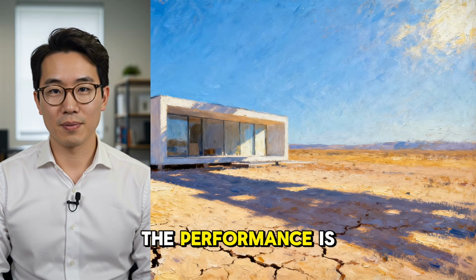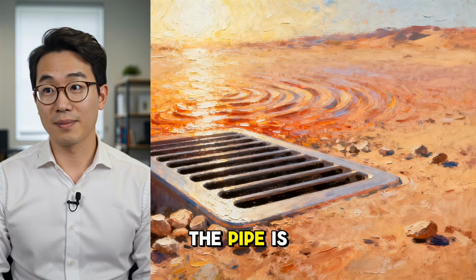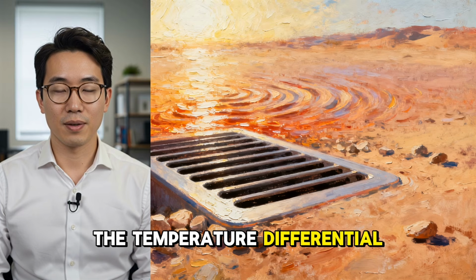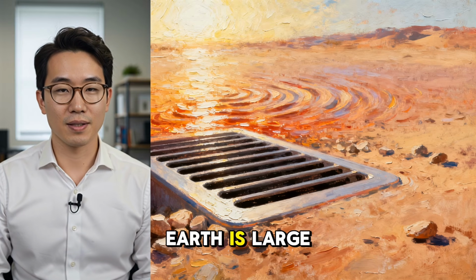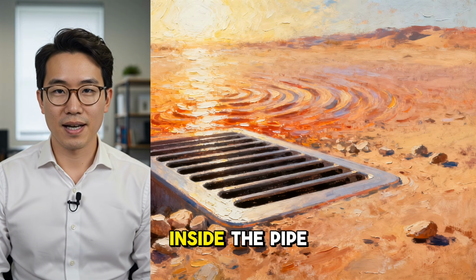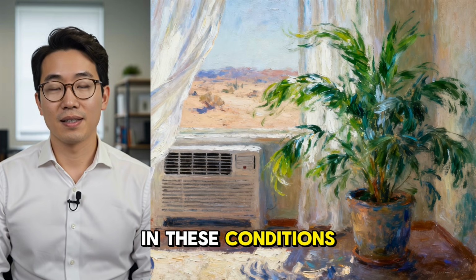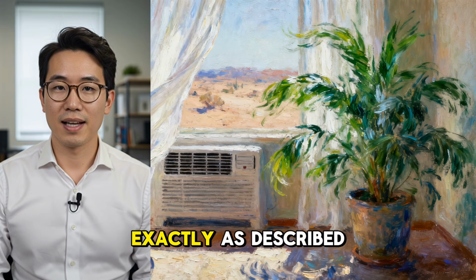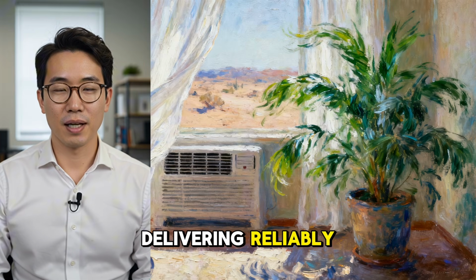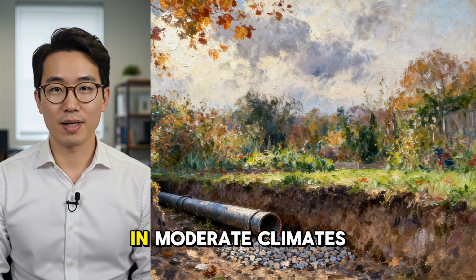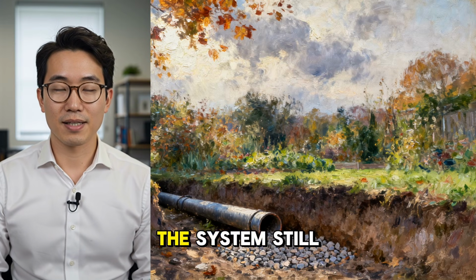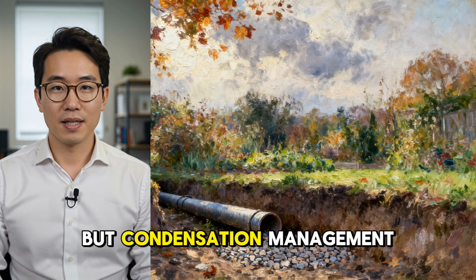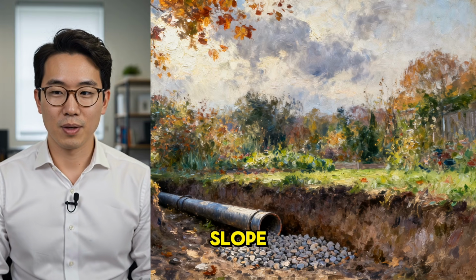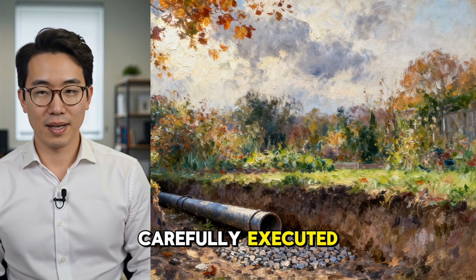In dry climates, the performance is exceptional. The air entering the pipe is low in humidity. The temperature differential between surface air and buried earth is large, and the risk of condensation inside the pipe is minimal. In these conditions, the system functions almost exactly as described, delivering reliably cooled air with no complications. In moderate climates with seasonal humidity, the system still performs well, but condensation management becomes more important, and the pipe slope and drainage design must be carefully executed.